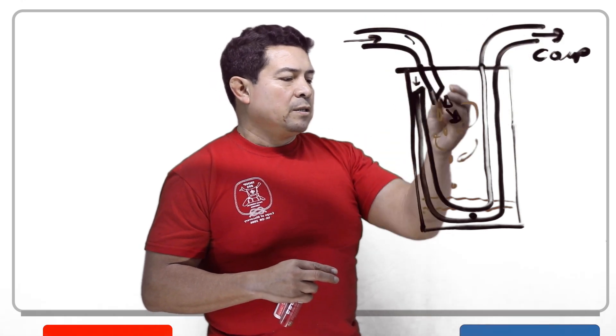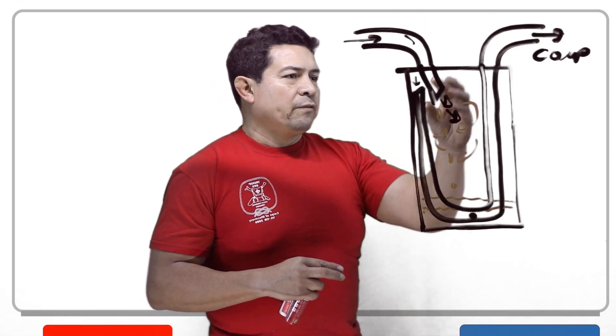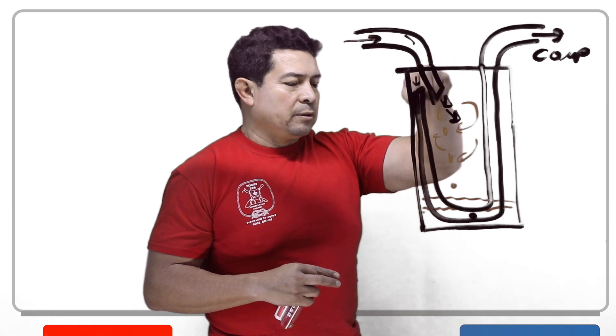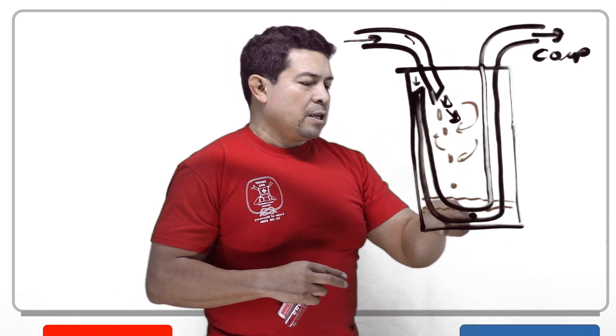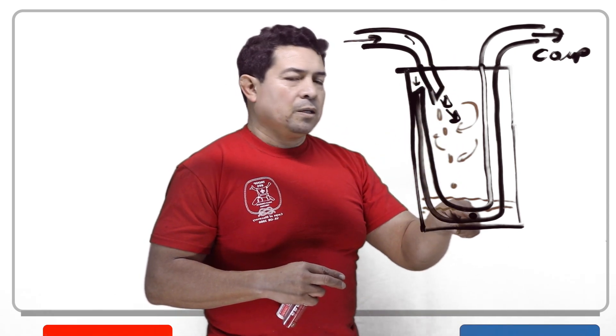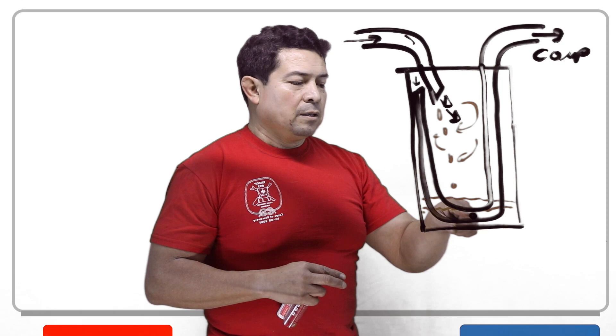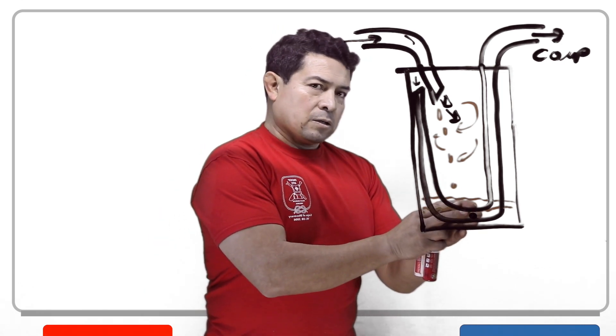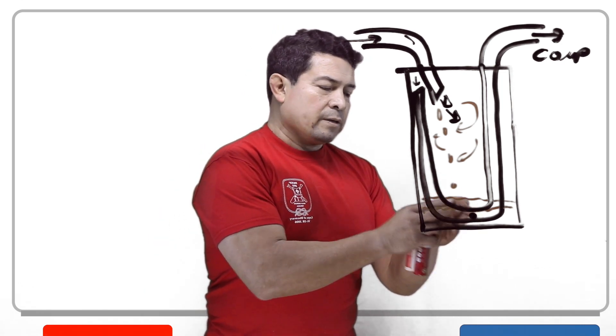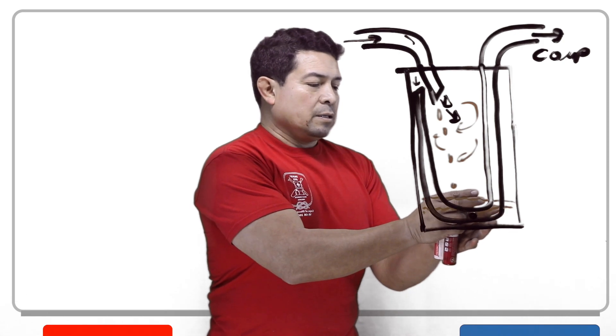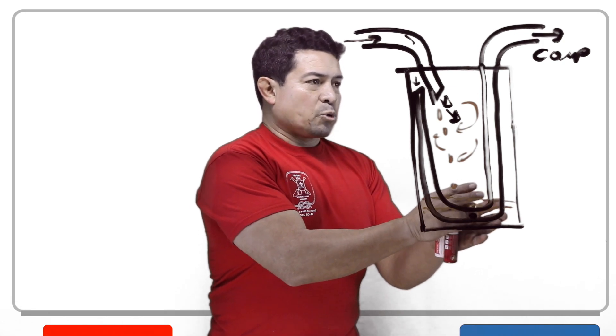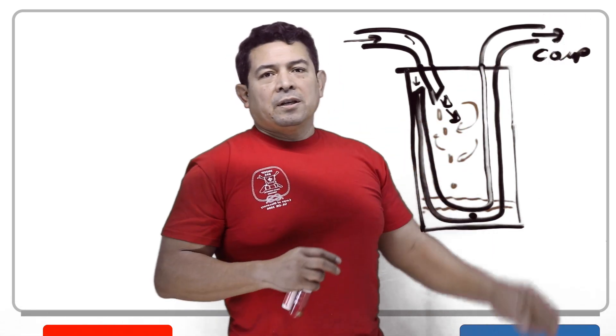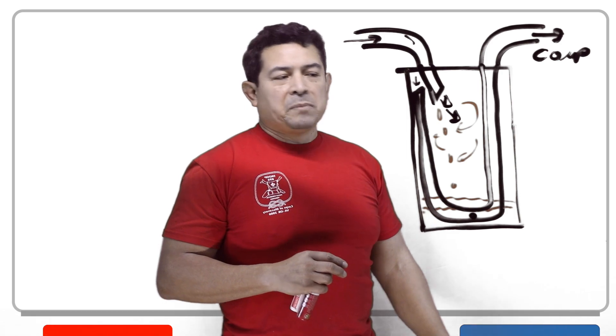It comes in, drips to the bottom, and all of the vapor gets drawn in through the top and travels through here. If there is any liquid here, because of the Venturi effect, it's going to draw it in, atomize it, and spray it so that when it goes back to the compressor, it's nothing but a mist.